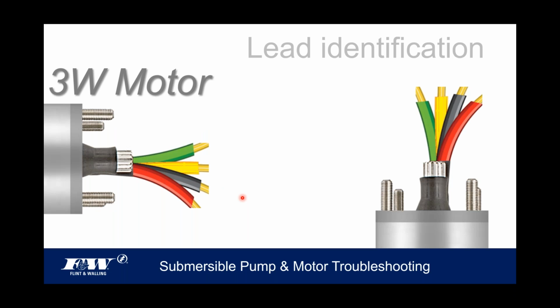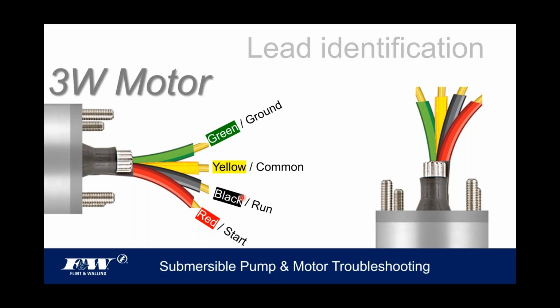On the 3-wire motor side, you've got the green ground, but you're also going to have a yellow wire, which is a common. Your black wire is going to be your run winding, and your red wire is your start winding. And so, again, understanding these colored cables and what each one of them contributes goes a long way here.